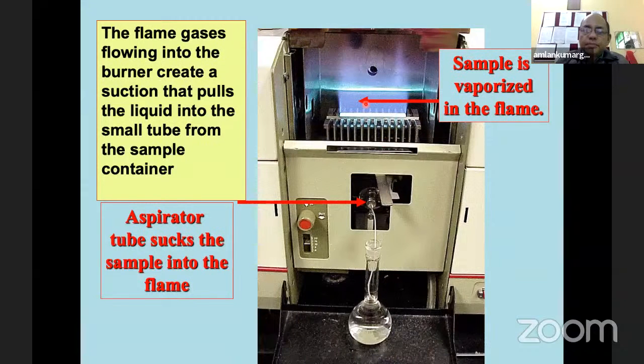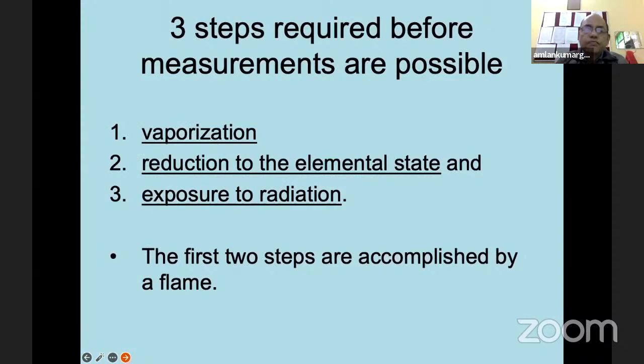This is the flame, this is the aspirator, and this is a capillary that sends the sample to the flame. The flame gases flowing into the burner create a suction that pulls the liquid into a small tube from the sample container. It is just similar to what we have done in flame photometer.